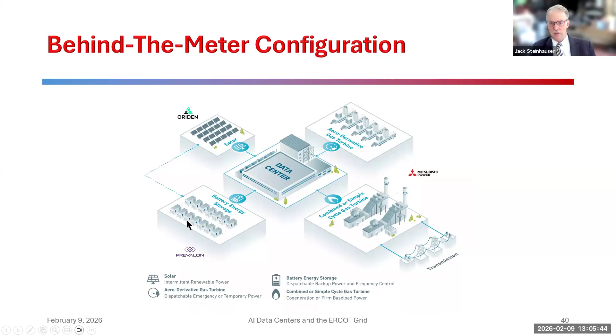The advantage of behind-the-meter co-location is that you can get to market fast. One of the problems people face right now is that it takes a long time to get one of these gas-powered electrical generation systems. So if you get hold of them, you can build your facility fairly quickly versus waiting for the grid to ramp up to meet your needs, which could take 5 or 7 years.